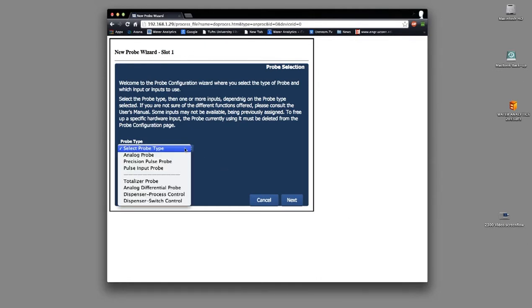The drop-down menu shows all the possible probe types. Above the dividing lines are real probes. These are 4 to 20 milliamp analog probes and pulsed output probes. Below the dividing line are what we call virtual probes. They're outputs that are created from the outputs of the real probes.